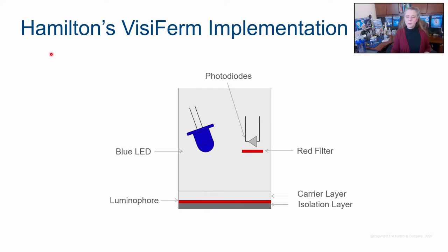So if we look inside a Hamilton VisiFerm, and every probe is similar, there are differences, and I'll talk about those in a second. Inside this cap, there is the blue LED laser. There is that carrier layer. Remember I said there's glass. The luminophore is actually on the outside of the probe. And then there's an isolation layer, silicone. That silicone only allows oxygen and no other gas to go through it to the luminophore. Inside the sealed environment, the blue light comes down, goes through the carrier layer, bounces back.